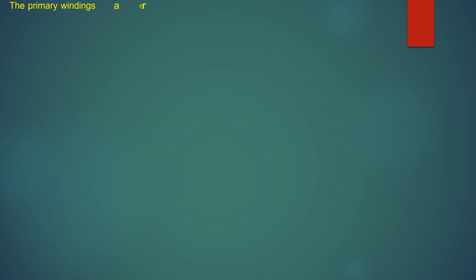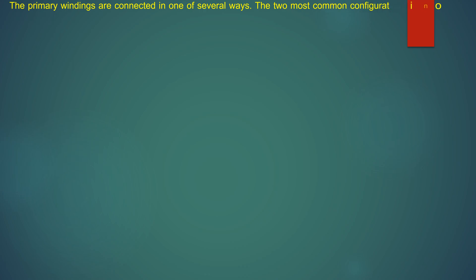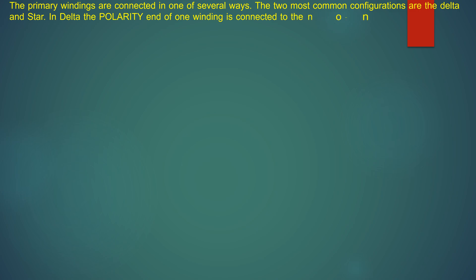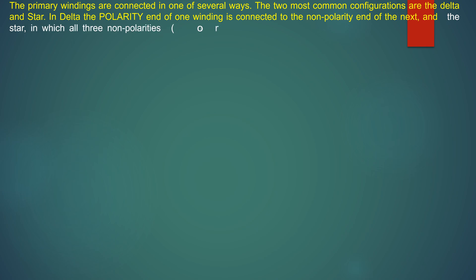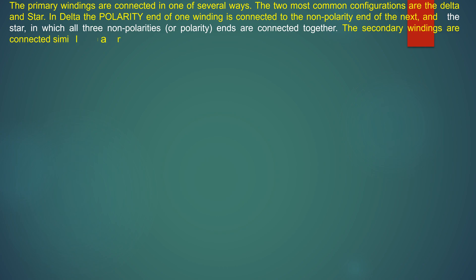The primary windings are connected in one of several ways. The two most common configurations are delta and star. In delta, the polarity end of one winding is connected to the non-polarity end of the next. In star, all three non-polarity or polarity ends are connected together. The secondary windings are connected similarly.